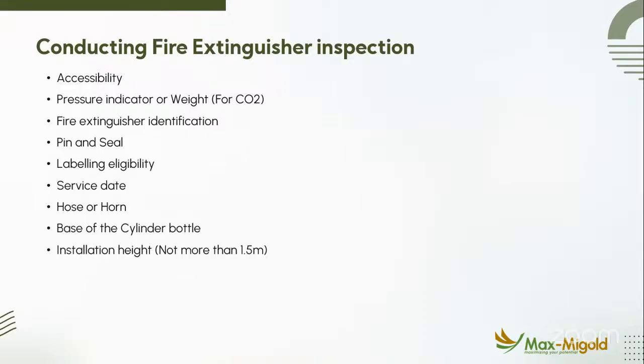Then fire extinguisher identification. That means, do you identify the fire extinguisher? Can we identify it? The pin and the seal, the label on the extinguisher should be legible. Then the service date should be clear. The hose or the horn must be in good condition. The base of the cylinder must not be corroded, and the installation height must not be more than 5 feet from the ground level for ease of removal during an emergency. Next slide, please.